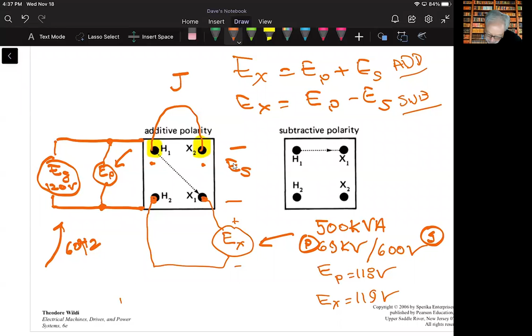We made the following determinations. We found that the primary voltage was 118 and the E sub x voltage was 119. He tells us, and we'll reason through this, that the polarity is additive because E sub x is greater than E sub p. So that, based on the conditions of the test, tells us it's additive.